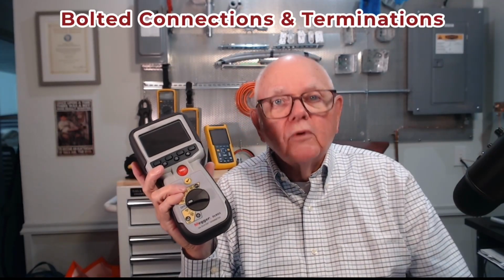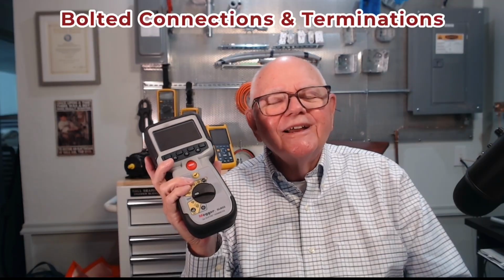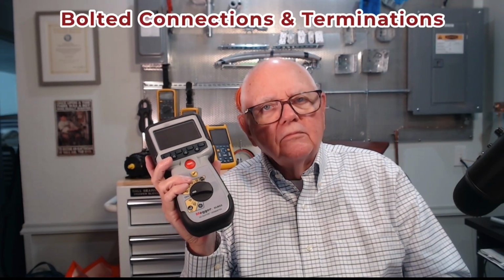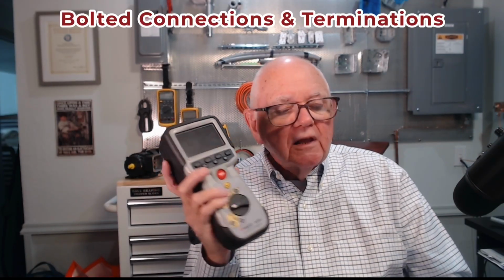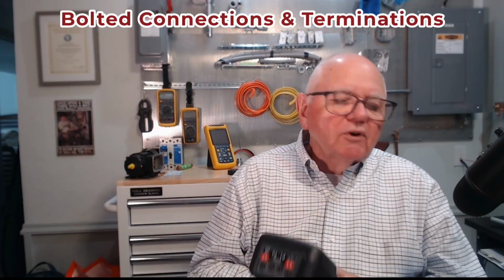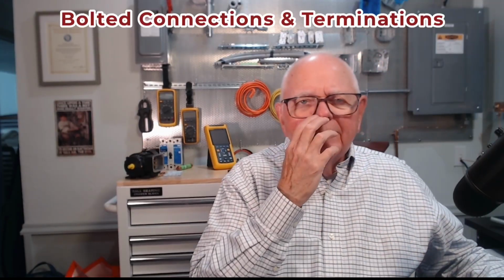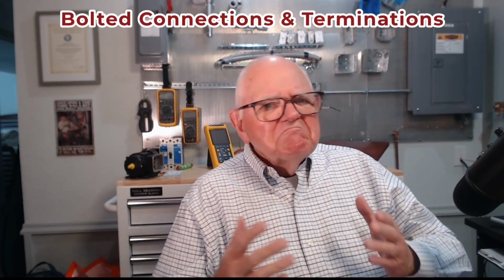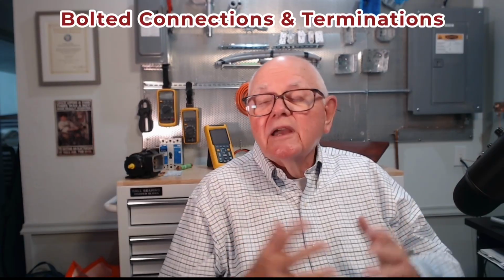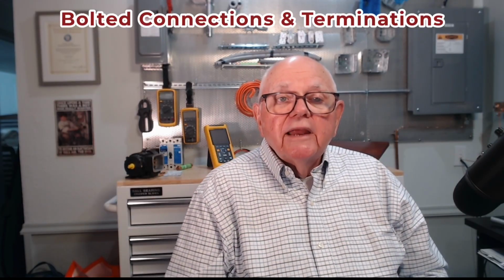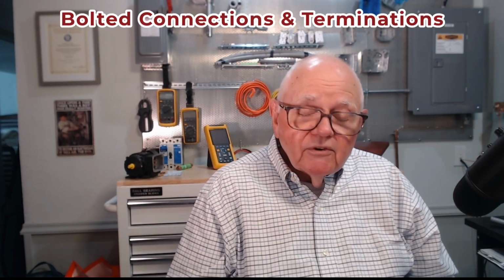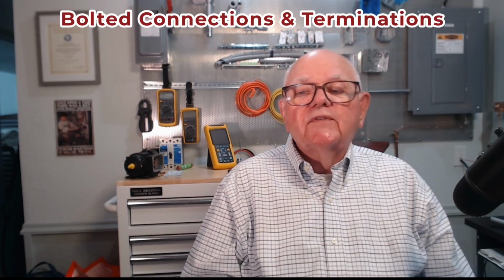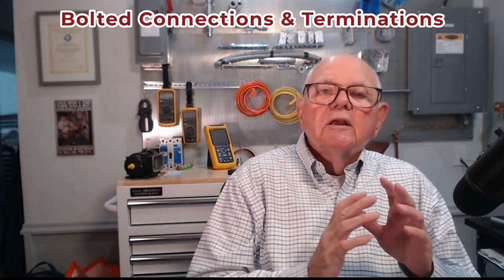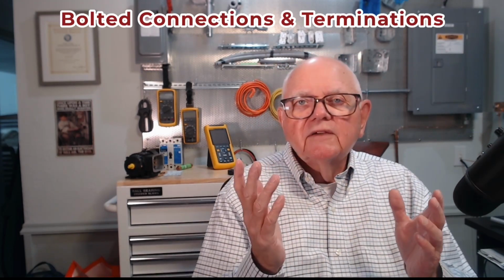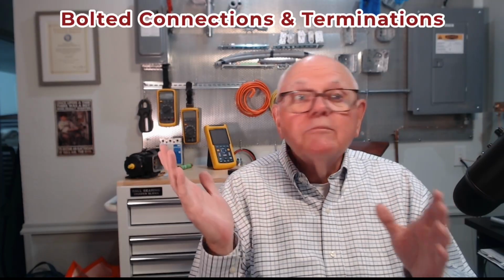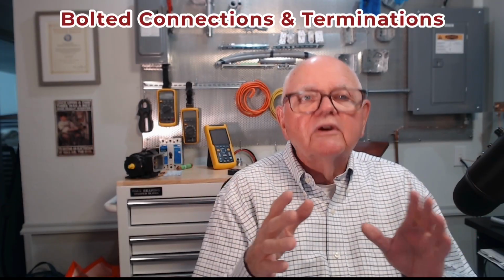0.000001 ohm would be 1 millionth of an ohm, or 1 micro-ohm. That's a pretty small value. So on my bolted connections, the typical values I might see would be somewhere in the range of maybe 10, 50, 80, to maybe 100 micro-ohms. Now, often follow your manufacturer's specifications on your equipment. So let's say if they specify something like 80 micro-ohms maximum reading or whatever, that's great.